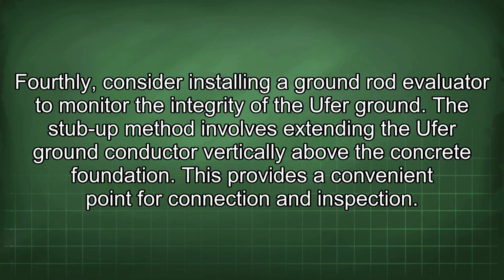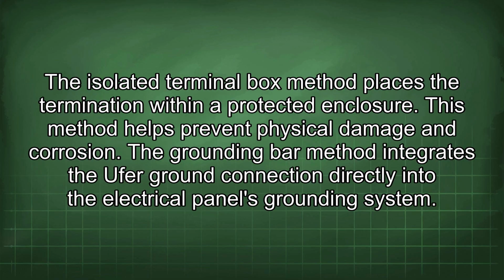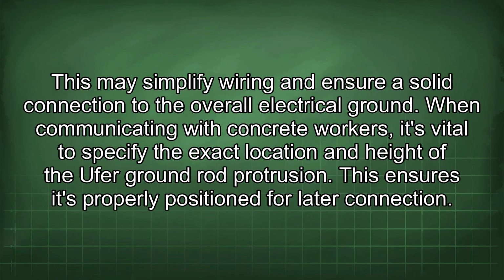The stub-up method involves extending the Ufer ground conductor vertically above the concrete foundation. This provides a convenient point for connection and inspection. The isolated terminal box method places the termination within a protected enclosure. This method helps prevent physical damage and corrosion. The grounding bar method integrates the Ufer ground connection directly into the electrical panel's grounding system. This may simplify wiring and ensure solid connection to the overall electrical ground.